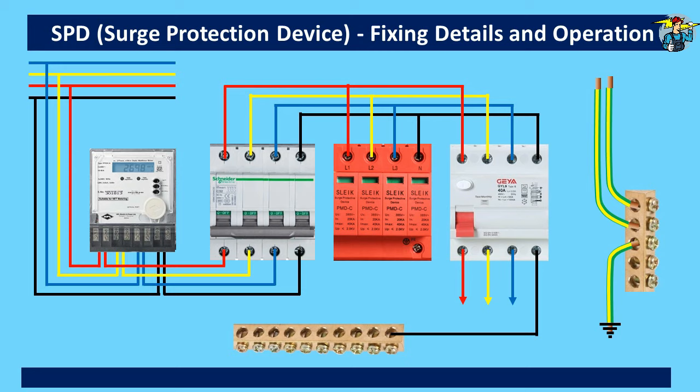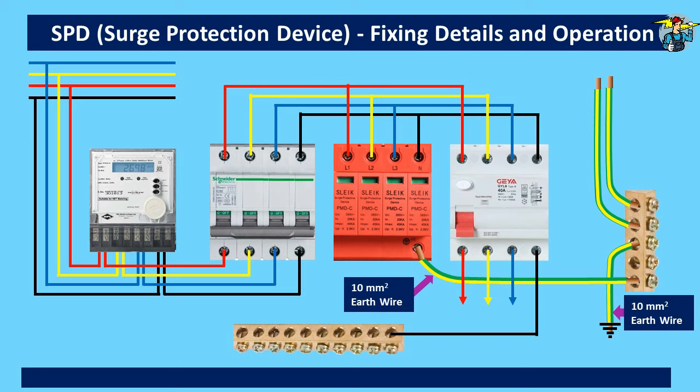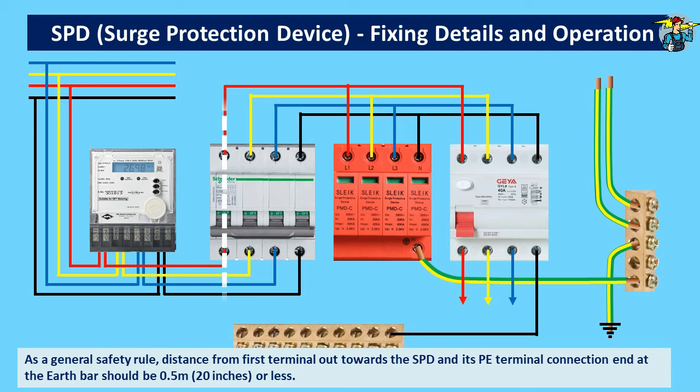You will see this SPD is actually connected parallel to the MCB. The protective earth terminal is made by joining the four L1, L2, L3, and N terminal connection ends together. In some SPDs you will see two earth terminals exist, but connecting one of them to the earth bar is enough. Now the SPD earth terminal is connected to the earth bar with a 10 square millimeter wire, making the total SPD grounding path occupy 10 square millimeter size earth wires. As a general safety rule, the length between the first terminal of the main switch and the earth bar terminal should be 0.5 meters or less.